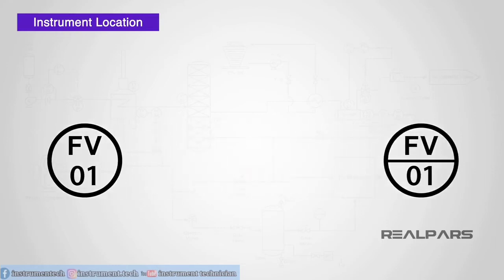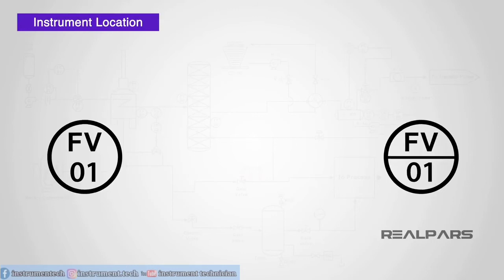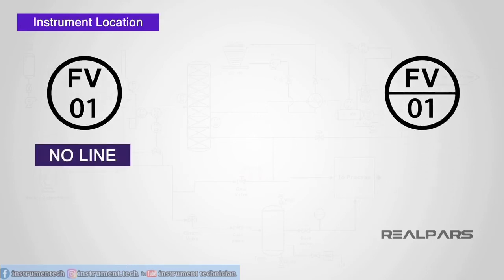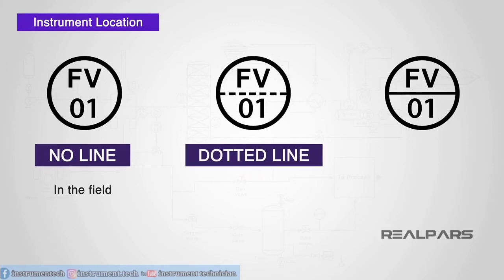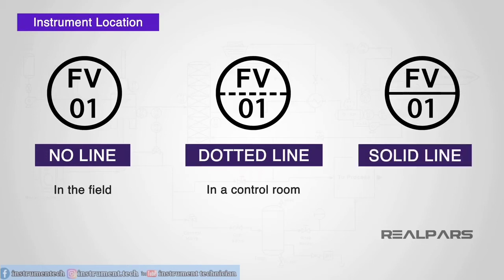The presence or absence of a line in the circle determines the location of the physical device. Let's take a look at how these are commonly represented. No line: the instrument is located in the field near the process and operator. Dotted line: the instrument is located in a control room, accessible to the operator. Solid line: the instrument is not directly accessible.